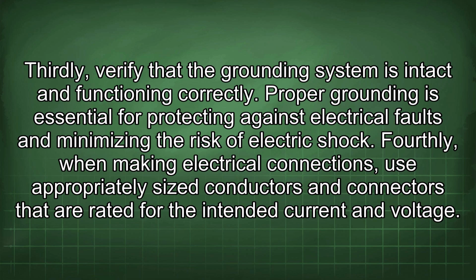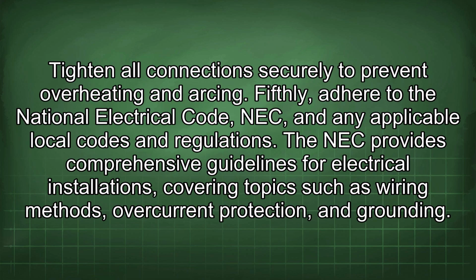Fourthly, when making electrical connections, use appropriately sized conductors and connectors that are rated for the intended current and voltage. Tighten all connections securely to prevent overheating and arcing. Fifthly, adhere to the National Electrical Code, NEC, and any applicable local codes and regulations. The NEC provides comprehensive guidelines for electrical installations covering topics such as wiring methods, overcurrent protection, and grounding.